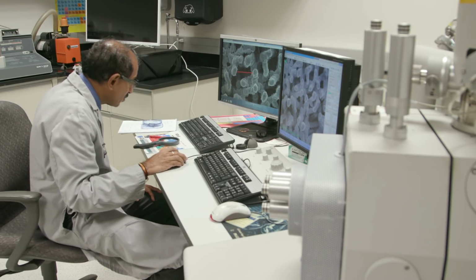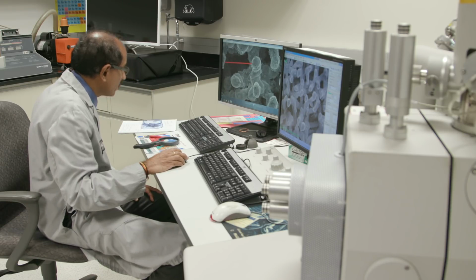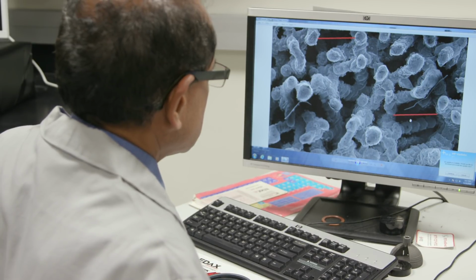So an example of one problem is, let's take that total knee tibial component that caps a bone resected tibia. In that case, was every component flat when it came out of additive manufacturing? And at times, for reasons we didn't fully understand, we didn't get the flatness that we wanted. Testing led Stryker to understand variables that could affect that flatness. And company engineers also addressed challenges of quality assurance. One of the benefits of additive manufacturing, it allowed us to make complex shapes.